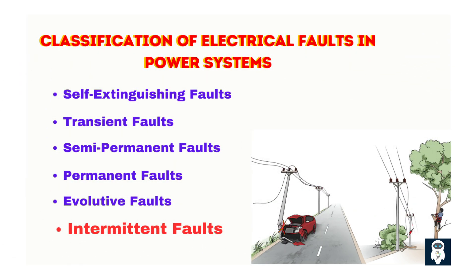Intermittent faults occur repeatedly over time, often due to environmental or mechanical conditions, and are temporary but can cause recurring disruptions. They are periodic in nature, triggered by specific environmental conditions, and may require system monitoring to identify root causes. Examples include swaying overhead lines contacting tree branches during windy conditions, and loose connections from vibrating equipment causing temporary faults under certain load conditions. These faults are difficult to diagnose, and preventive measures such as vegetation management or line tightening are often necessary.